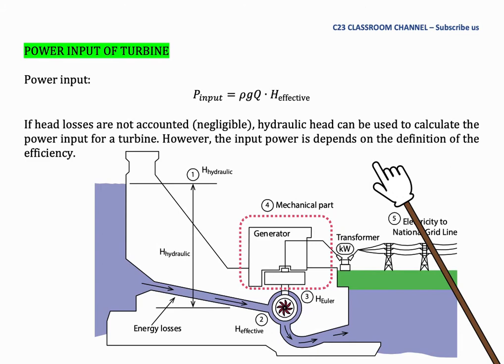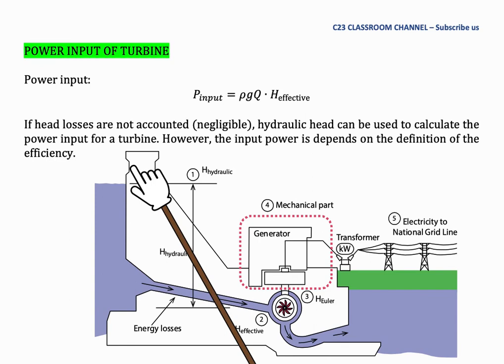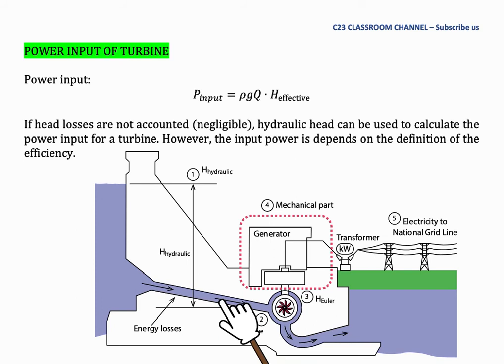The net head that occurs in front of the Francis turbine inlet is called the effective head, which becomes the input for the Francis turbine. Power input of the turbine can be written as P_input = ρgq × H_effective. If head losses are not accounted for, hydraulic head can be used to calculate the power input. Normally, engineers will design the Francis turbine near to the dam to neglect the energy losses in the pipe system.